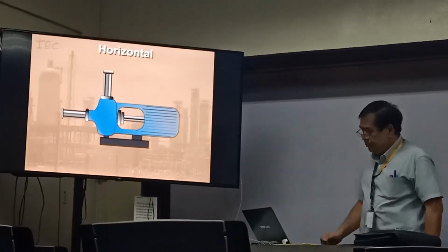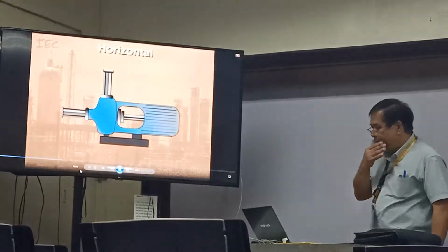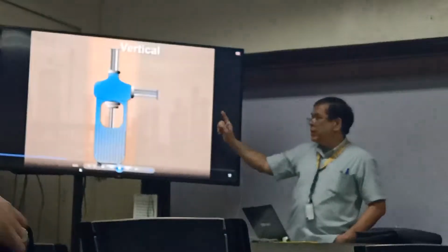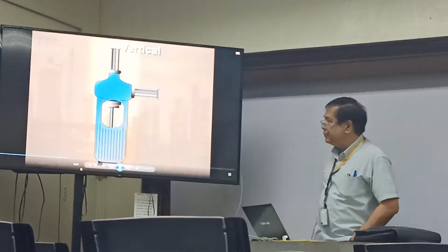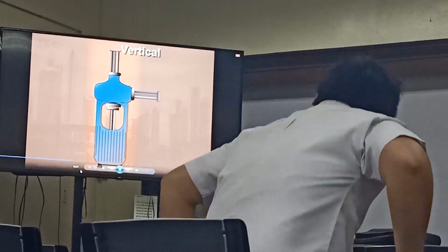If a pump is said to be horizontal, it means that the shaft is horizontal to the ground. Horizontal seems to be the most common type in industry. However, vertical pumps are more compact, winterize better, and tend to have lower installation costs.